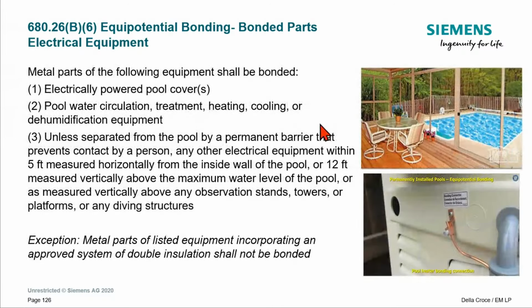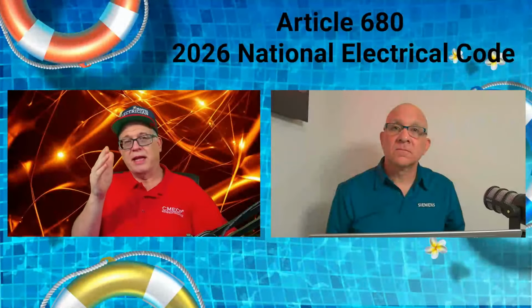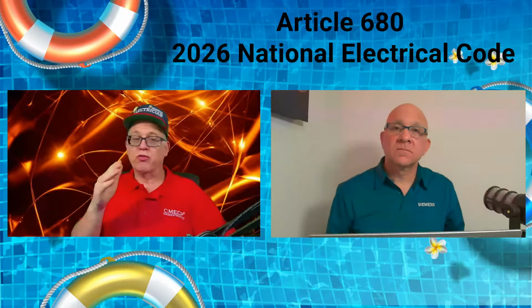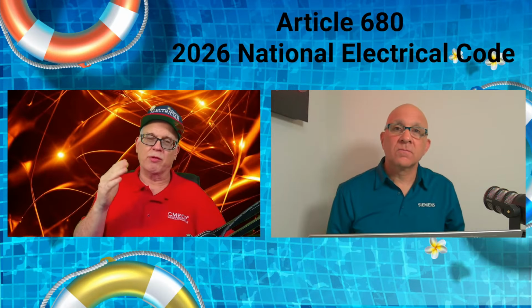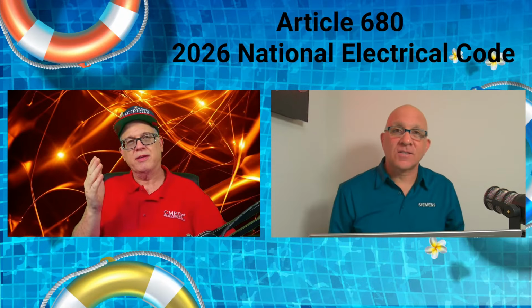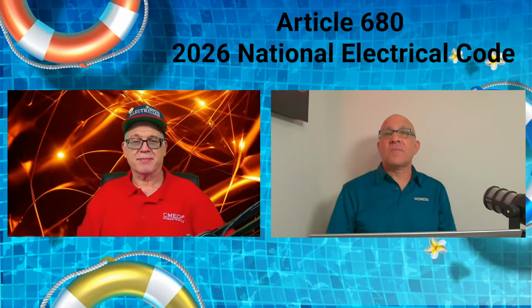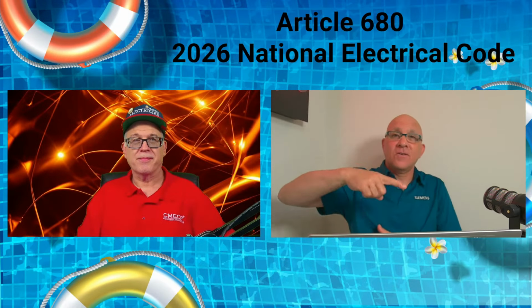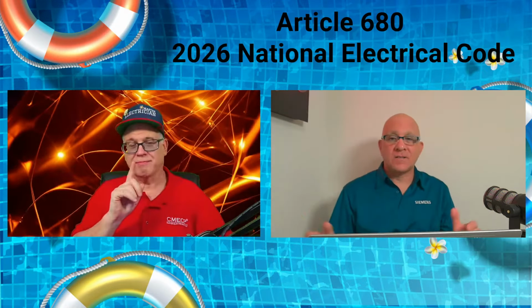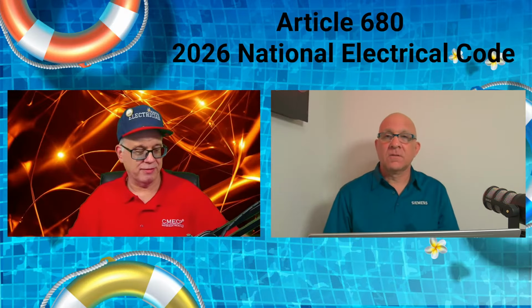Well, whoa. What about that steel reinforced that's all bolted together? We asked whether or not we had to do one piece or bring it to all of them. But yet here in a lanai, it's all still bolted together, and we're saying we really only have to bring it to one piece. I think so. My inclination is yes, on that steel frame, that it's one location, one shot and you're done.